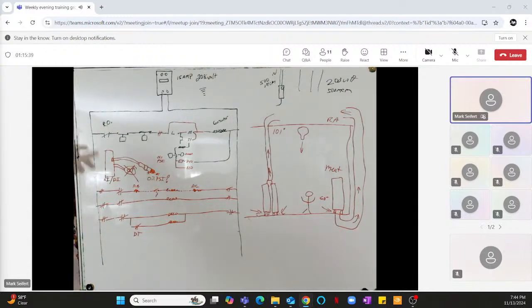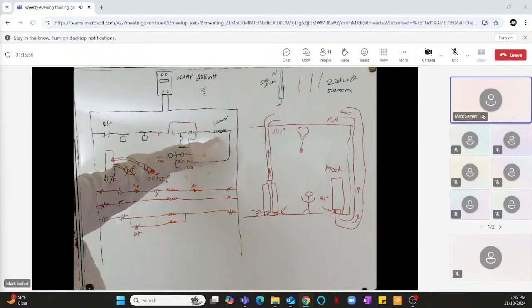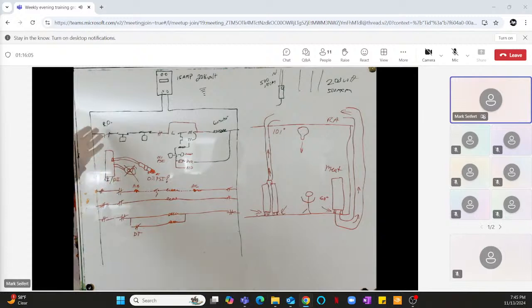So you go to reset it and the compressor doesn't turn on and it trips on oil and it has a CT. Well, now you've got a handful of issues you've got to look into. You've got to realize, why didn't the CT tell the controller that the compressor is not drawing any amps? That's the first thing. But then again, that's just a secondary problem. Why did the controller call for the contactor to come on and it didn't come on? Or maybe the contactor came on and it's a trip breaker? So the controller called for it to come on, the breaker was tripped, but why did the CT tell it was running? So it comes with its own issues.